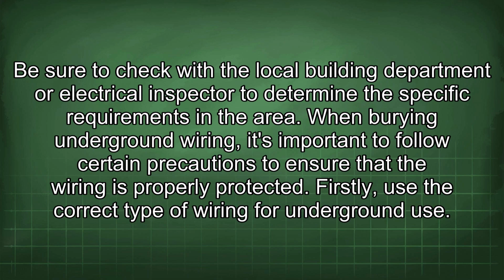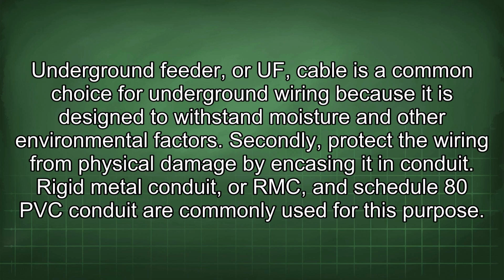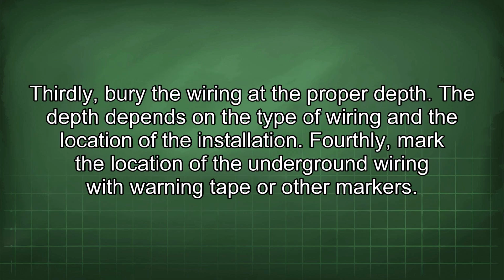Firstly, use the correct type of wiring for underground use. Underground feeder, or UF, cable is a common choice for underground wiring because it is designed to withstand moisture and other environmental factors. Secondly, protect the wiring from physical damage by encasing it in conduit. Rigid metal conduit, or RMC, and Schedule 80 PVC conduit are commonly used for this purpose. Thirdly, bury the wiring at the proper depth. The depth depends on the type of wiring and the location of the installation.